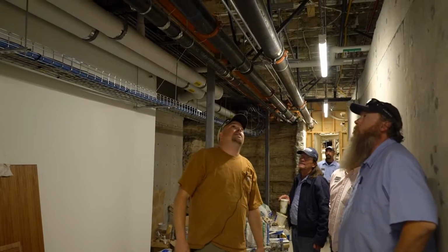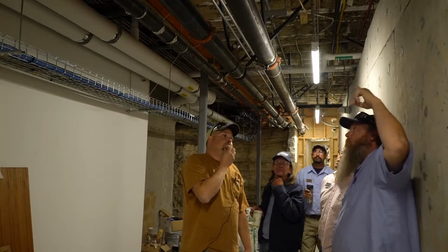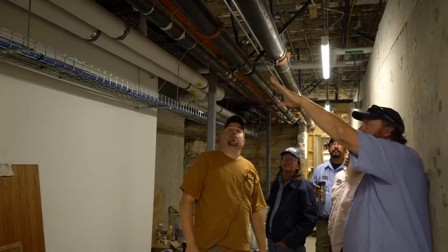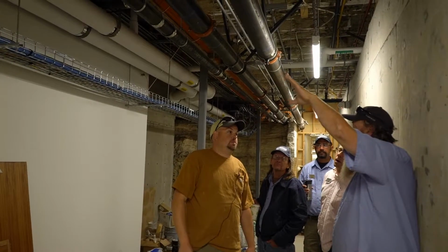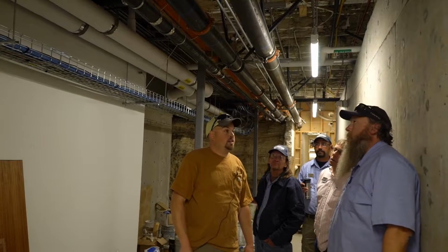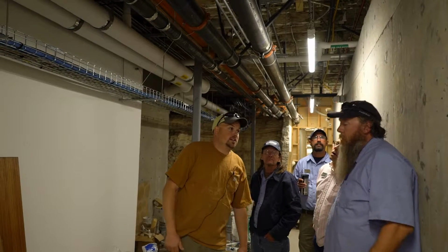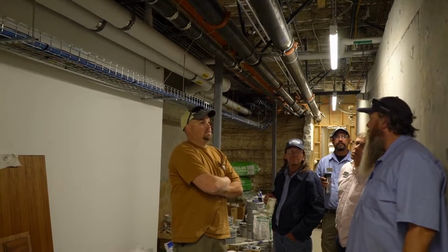And since you're tying into the old system that still feeds the wing on the domestic, was it engineered, and are we gonna see a test and balance report? You should have a test and balance report. Like I say, I'll look into that with my office and see if they actually got one back from Swank or whatever. I guess the reason I'm asking is the original system, I don't even know if there were circuit setters in there.